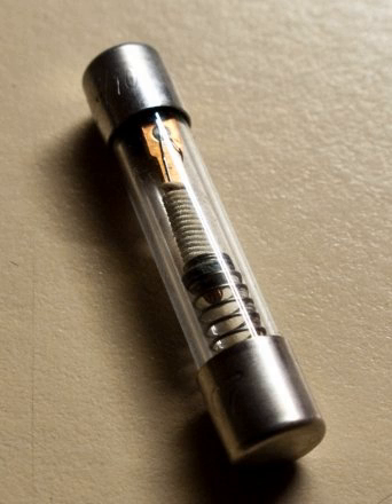HRC fuse links are equipped with handle straps for handling, which can be either live or de-energized insulated. A fuse handle is required to insert the fuse links into or remove them from a fuse base with one pull. When live, HRC fuse links may only be replaced by a qualified electrician with suitable protective equipment. The protective equipment must include at least one push-on handle with permanently attached leather cuff, a helmet with face protection or a flame-retardant hood and closed, flame-retardant work clothing.